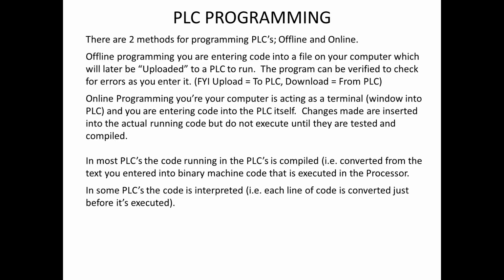There are two methods of programming PLCs, either online or offline. When you're programming online, you are programming code right into the PLC, and usually those aren't executed until they're tested and compiled. I will say that in some PLCs the code is interpreted, which means that it's read and then converted just before execution. So you need to know whether your PLC is interpreting code or compiling it.